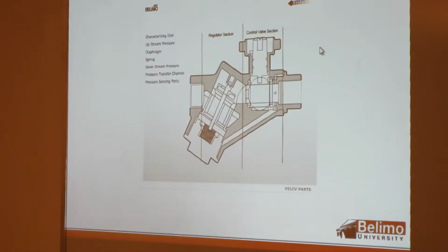Various parts of the PICCV, well, we have the characterizing disc. Like I said, this is part CCV. We look at the upstream pressure here. Got your diaphragm down here with your spring, then the downstream pressure. Then once you compare those two through the pressure transfer channel here and pressure sensing ports, that's what adjusts that pressure regulating device.